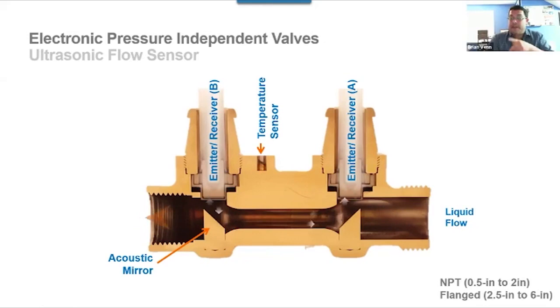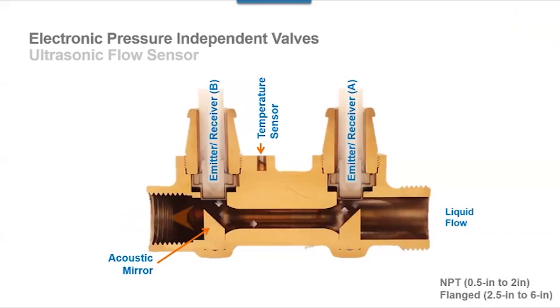I'm sorry, if I can throw in here, a lot of the test and balance folks in the audience are used to using clamp-on ultrasonic meters. And that has probably been in part the difficulty that you were referencing earlier. To clarify, most balancers do not have in-stream access to ultrasonic measurements. And that's really the fundamental difference of why this ultrasonic is probably going to be a lot more dependable than the ones that we're actually using and referencing on the outside of the pipes. Exactly. I've heard a lot of horror stories about the clamp-on ultrasonic meters. You can't get a good place for the plate. You don't get a good reading. Well, in this case, it is an in-stream device, which certainly helps immensely with that.